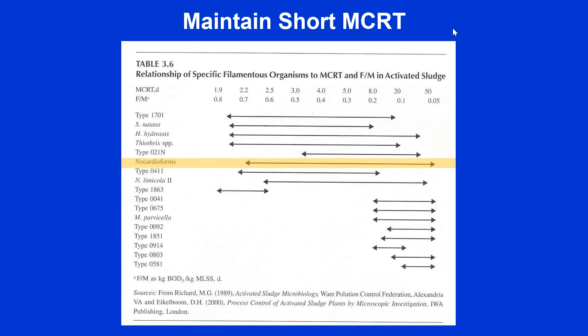There is the same treatment plant after we, one, created an overflow weir so there wouldn't be foam trapping. Two, it was a 3-pass system and we got rid of one pass and just did it down and back. Well, they had a 3-pass system that ran in parallel. But what we ended up doing was running in plug flow in 2 passes down and back, and wasted a ton of sludge, sucked a ton of foam off the top of the layer. The street department came in and sucked foam for 2 days. And then they started adding sodium bicarbonate to the mixed liquor to raise the pH to over 7.